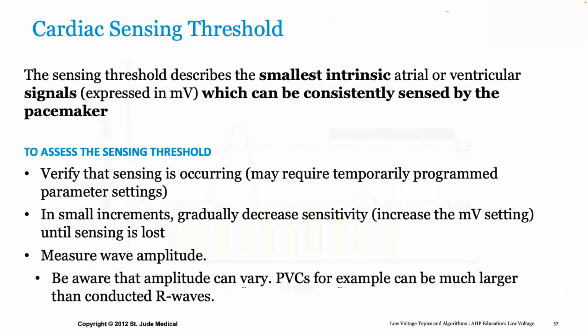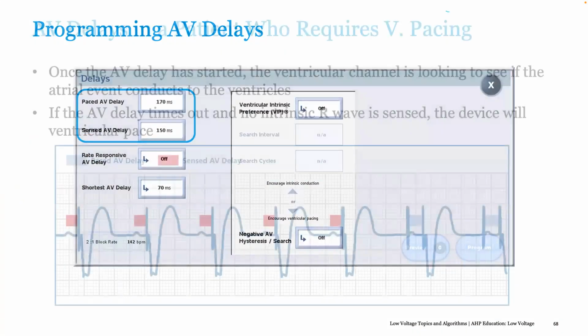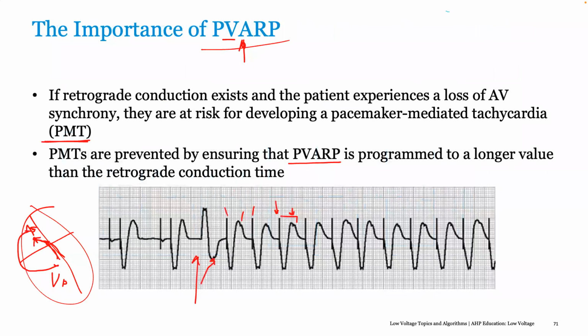Yeah, that'd be great. Again, that's Medtronic's PVAB. Medtronic normally has an absolute blanking period of about, I think, 30 milliseconds. And then partial will add an additional 150 milliseconds on top, where basically it will blank anything based on the sensitivity that you've set. So for instance, if you're seeing a far-field R wave on the atrial channel, and it's in partial, and you're still seeing it, the difference with partial plus is that it also adds an additional 150 milliseconds blanking period, but partial plus will automatically adjust the sensitivity and decrease it. So you're less likely to see any far-field R wave oversensing on the atrial channel.